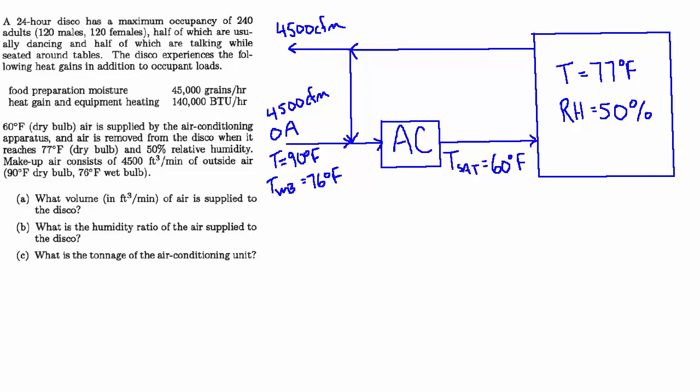Makeup air consists of 4500 CFM of outside air which is 90 degrees dry bulb and 76 degrees wet bulb. They have three questions for us: A. What volume in CFM of air is supplied to the disco? B. What is the humidity ratio of the air supplied to the disco? And C. What is the tonnage of the air conditioning unit?